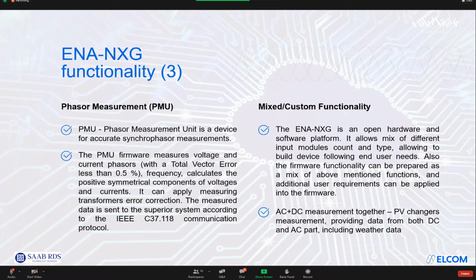Or we can run the ENA NXG as a so-called phasor measurement unit. This is a device usually used by transmission system operators. The meter measures very precisely the phase amplitude and angle of each voltage and current phase, and sends it using a standardized protocol into central software. This is the PMU, used in so-called wide area monitoring systems. People from transmission system operators know this functionality very well.